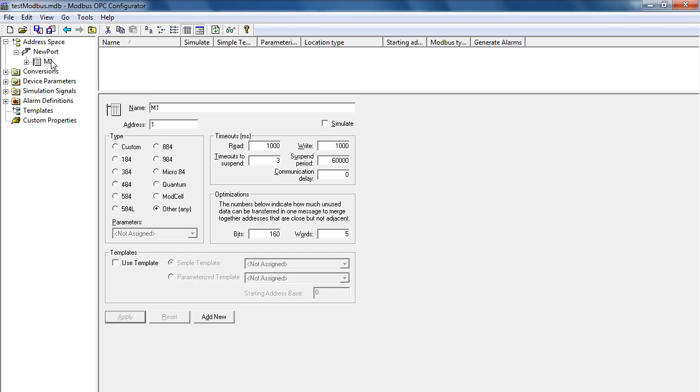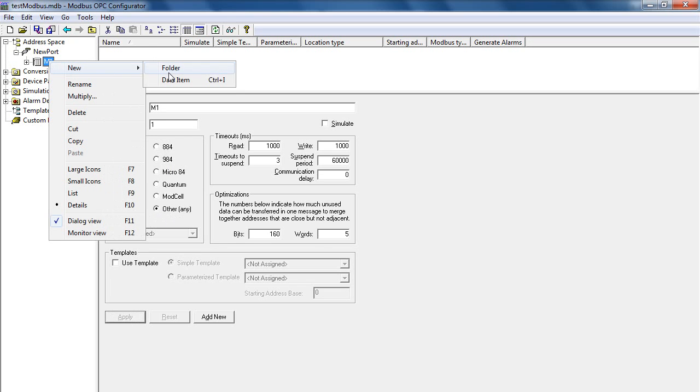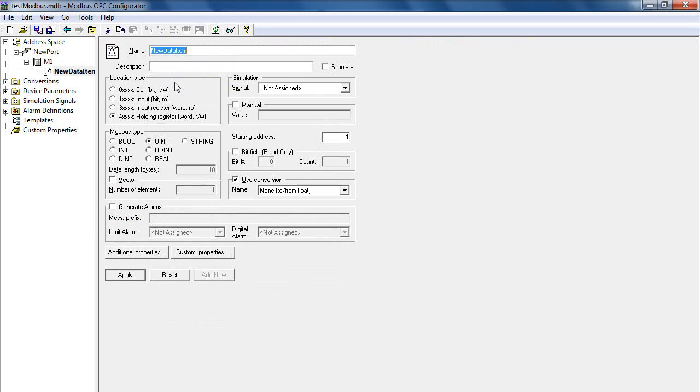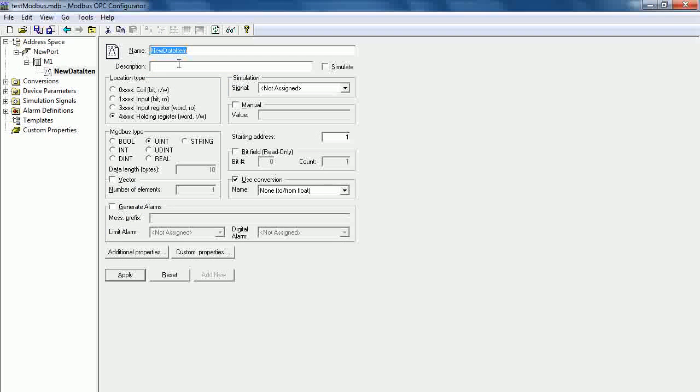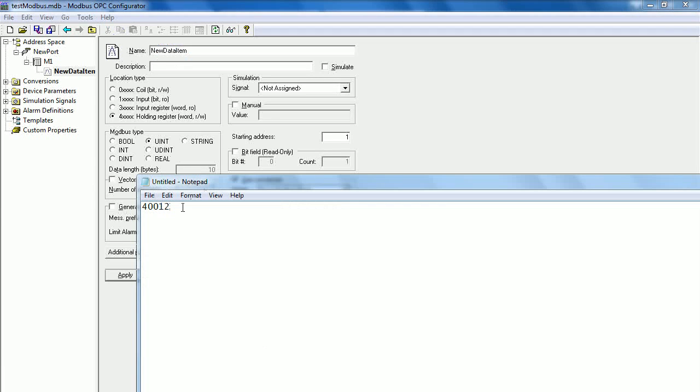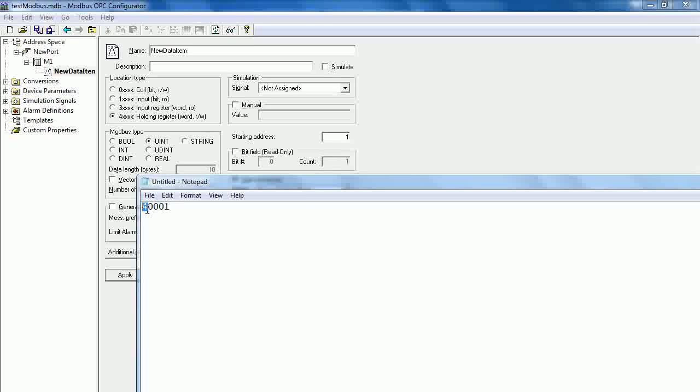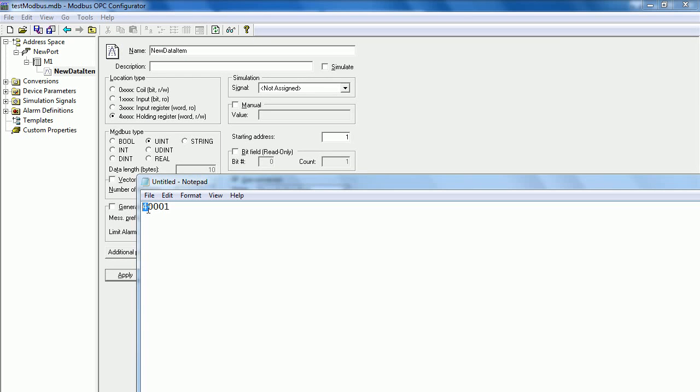Right click on the device and select New Data Item. In this example, I will be connecting to the register address start at 1. Then you need to specify the location type as Holding Register, because it starts with a 4 that identifies the Holding Register.